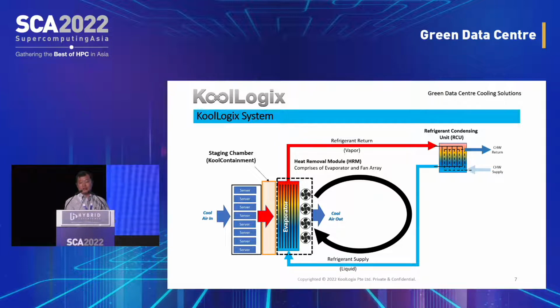So the staging chamber and the HRM are combined together and form a rear door heat exchanger, basically. Through that, the hot air goes through the evaporator. That's a rear door heat exchanger. Okay? It picks up the heat, and the heat is removed by causing evaporation. Actually, boiling happens in our case, but boiling is another form of evaporation.